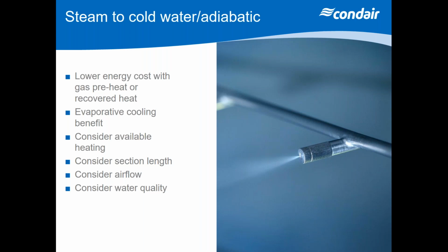You've got to also consider the airflows, because obviously if you're trying to change to an evaporative system, there is a certain level of velocity the air will pass through that media. Now, if the air is too fast, then the evaporative system will not work effectively at all. But also, you've got to look at your water quality as well, because you can't spray, for example, without having RO water in an in-duct system. So all those things you consider if you're going to want to go to a cold water system. It's not exactly straightforward, not a quick fix and change out.